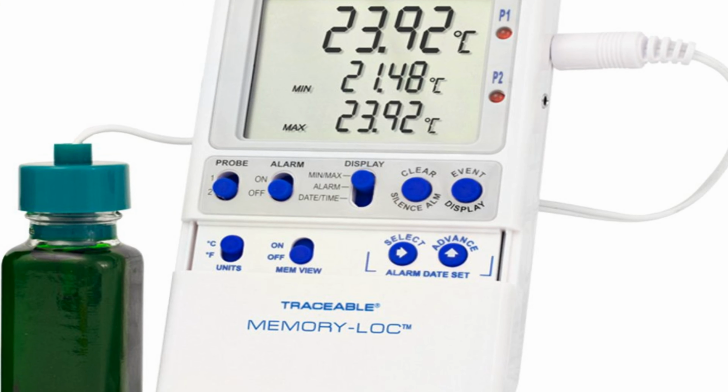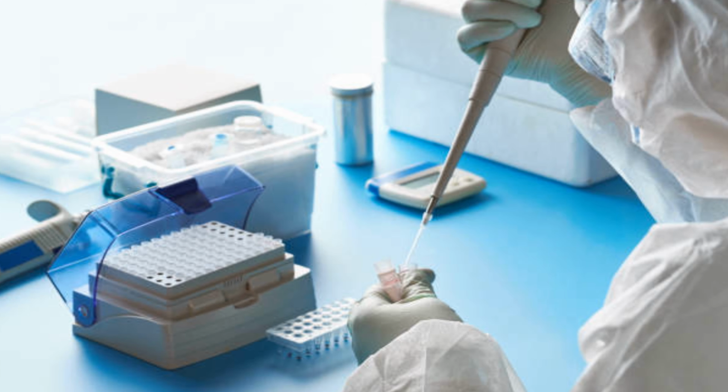So anyway, story time. When I came to work, the first thing that I do in the morning is take temperature logs from the temp logger thermostat. If you guys don't know what a temp logger is, it's basically the temperature monitors that are connected to a sensor that you place either in the refrigerator where the investigational product is, the ambient cabinet where investigational product can be, or the freezer where samples, in our case our frozen samples, go into, and we ship our samples overnight.